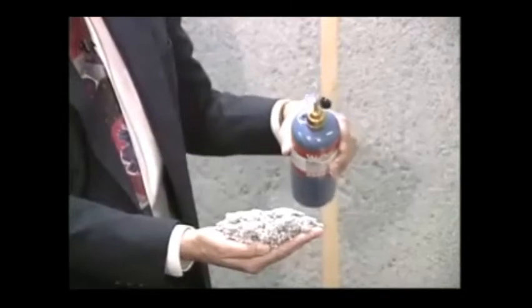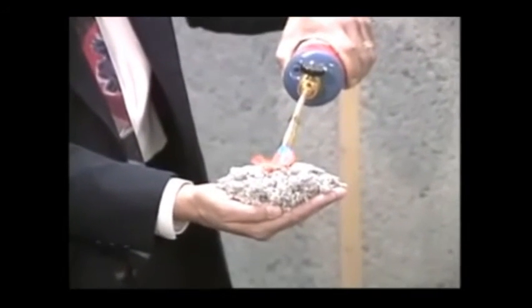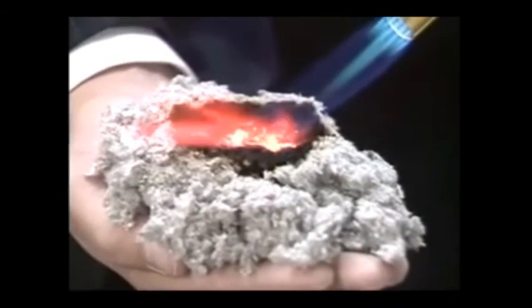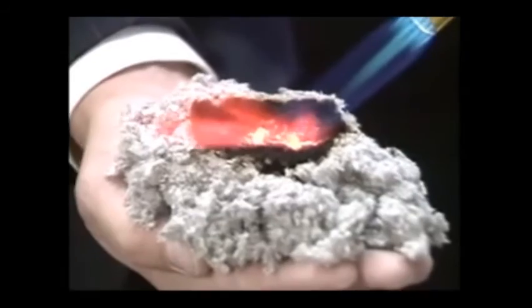The cellulose does act as a good insulator and would therefore also keep the heat of the fire within the building. However, once the protective gypsum wallboard falls away, the cellulose itself is still remaining in place and protects the structural elements. It does not burn through, but rather forms a char layer because of the fire retardant effect, so it can stay in place longer.